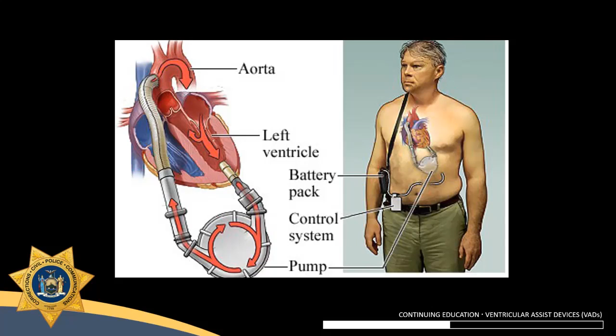later model is because it uses more of a corkscrew drive. It doesn't use the rotary impeller anymore. They found out those rotary impellers can cause blood clots and they break a little more easily. So the later models now use, this is the LVAD device itself right here, a screw drive that's inside, and it turns around and around and pushes the blood out without the rotary action of the rotary impeller. But otherwise the function is largely the same.